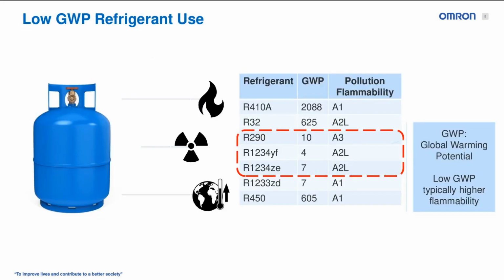And when we're talking about low GWP refrigerant use, we're talking about moving from high GWP levels like R410A and R32, which are lower flammability levels, the A1 flammability, and A2L, which is semi-flammable. We're moving to lower GWP levels than that, so everything that's circled in the dotted red box. So we have double-digit and single-digit levels of GWP and a higher flammability level. So we're lowering ozone depletion, we're lowering global warming potential, but we're having to deal with the semi-flammability.